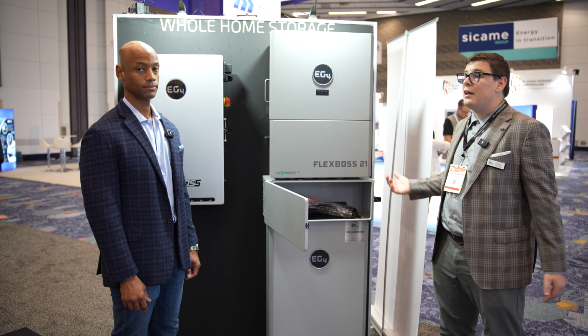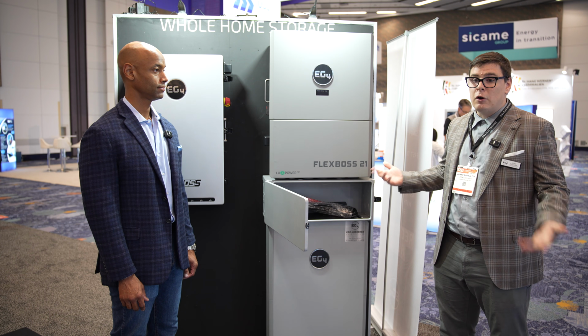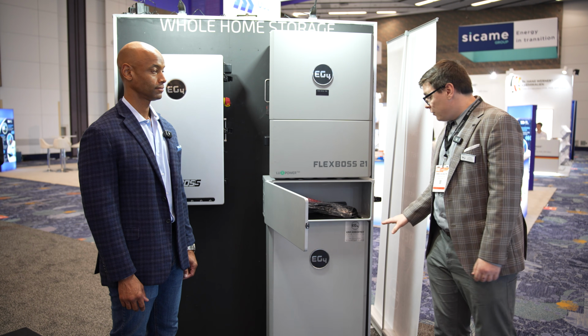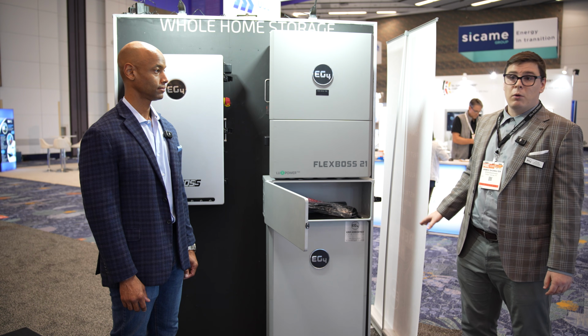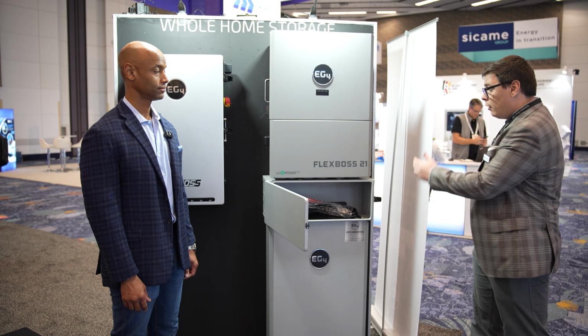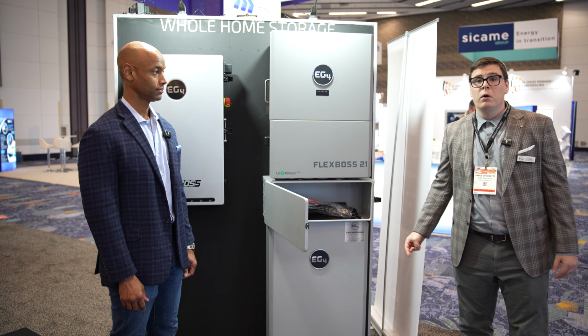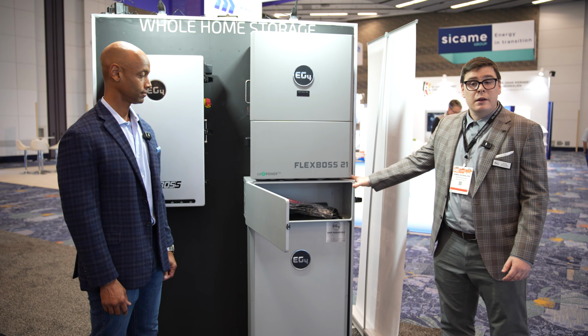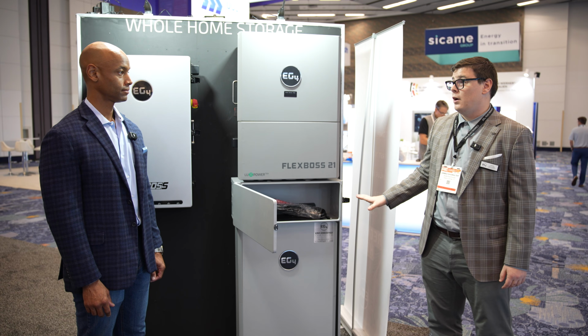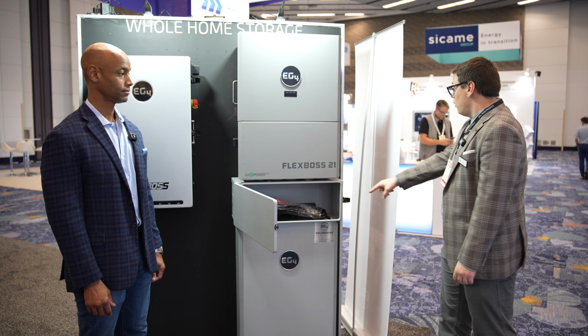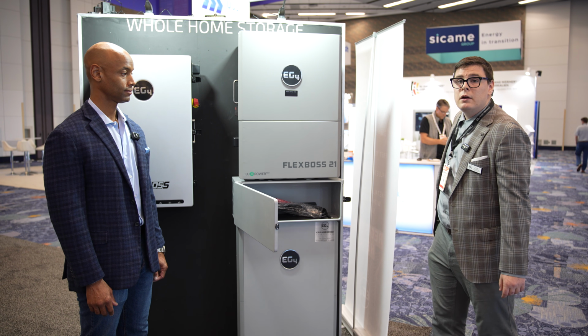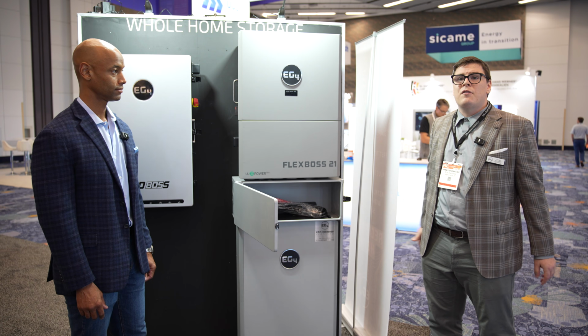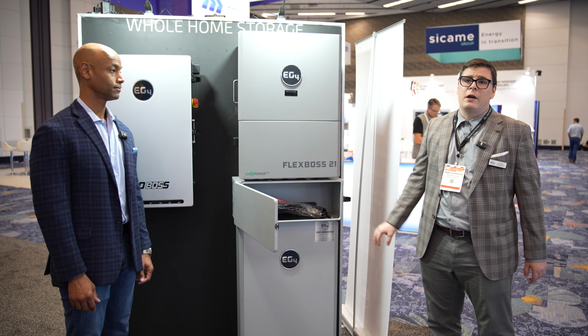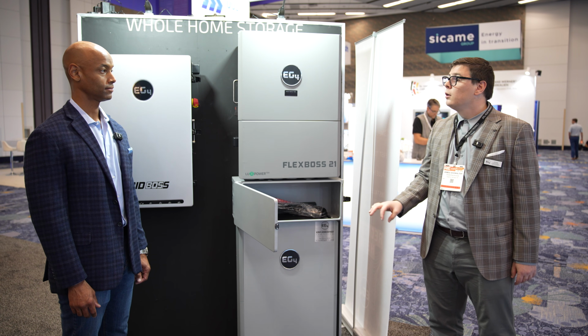You don't need to buy anything but our quick connect cables and our Ethernet cables. So if a customer buys 2 batteries and wants a 3rd, you're going to hang a 280 pound module on the wall and use our pre-made conduit box, which saves a tremendous amount of time and money. You run the cables right to that battery, and you're out of there.